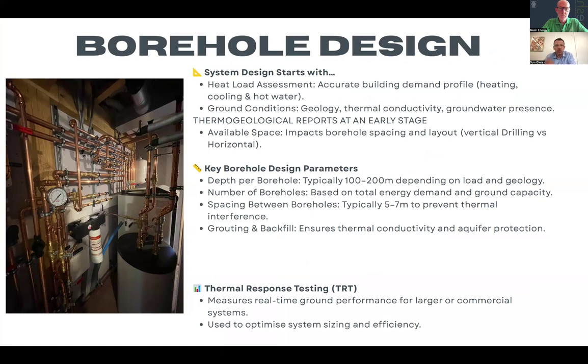The next thing I'm going to discuss with you is the design of the borehole system. To do the design, depending on the size of the property and the whole project, in some cases we would recommend doing a thermal response test, which is TRT, which gives us really good information about the geology, the aquifer, and the thermal conductivity of the borehole. We would recommend this in larger commercial or large domestic properties where we've got potential for multiple boreholes, because doing this can reduce the number of boreholes quite significantly, and then of course reduce the capital cost of the system.